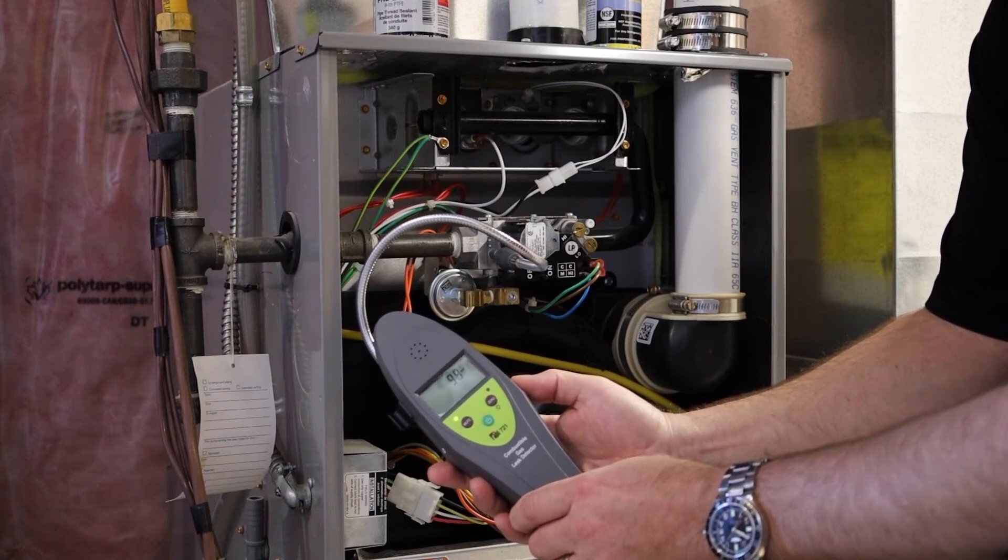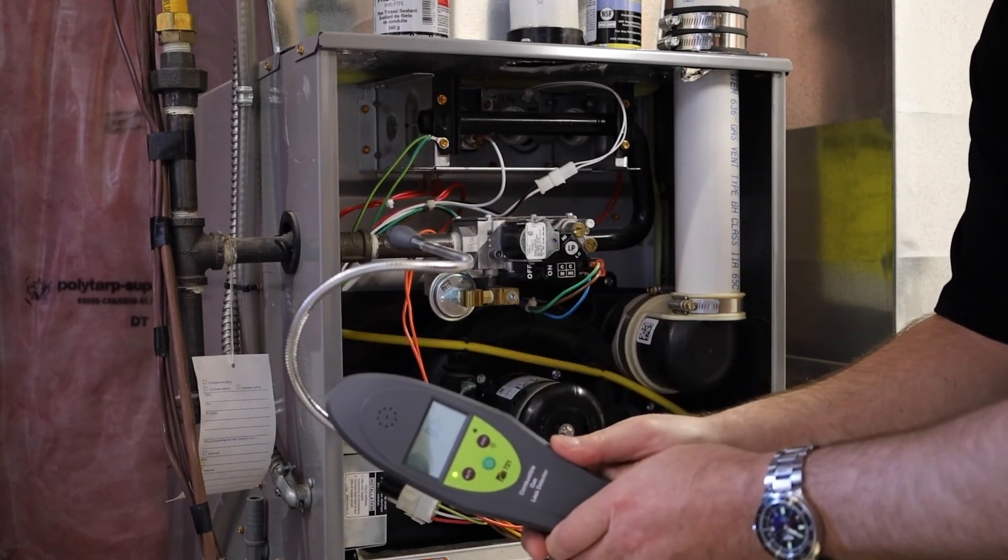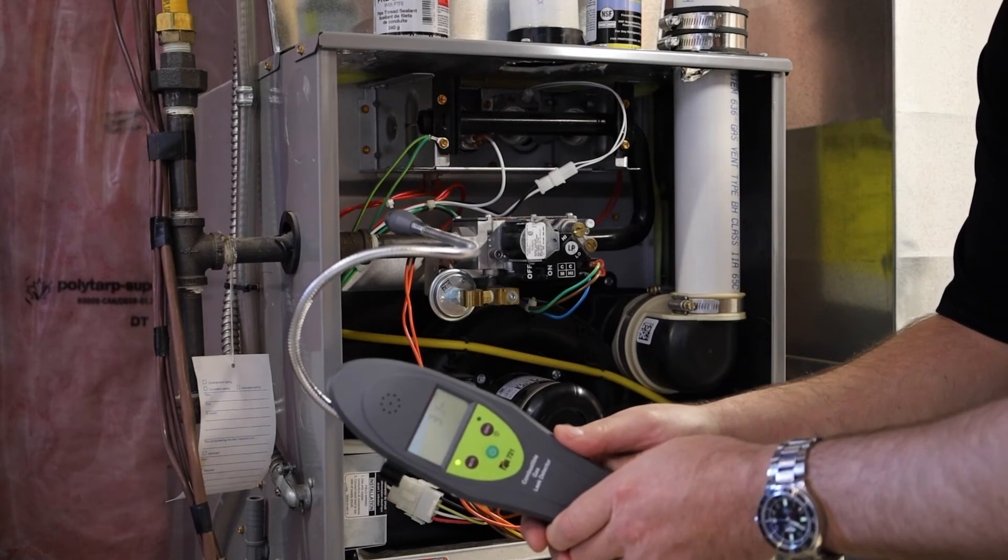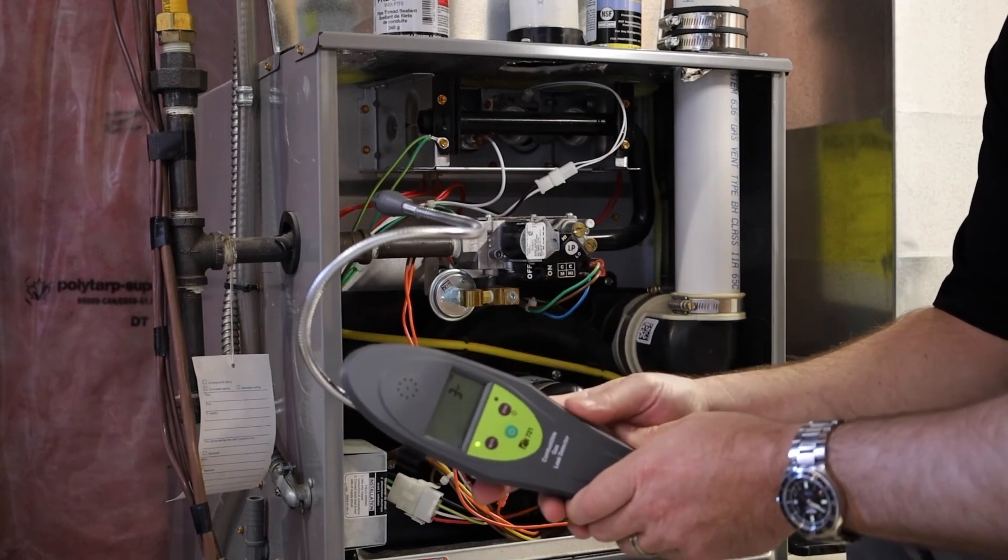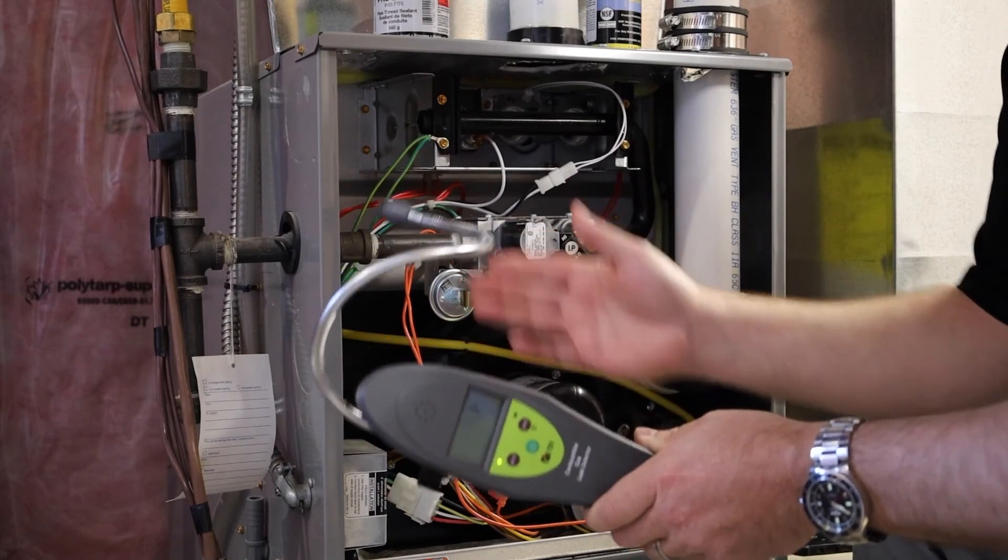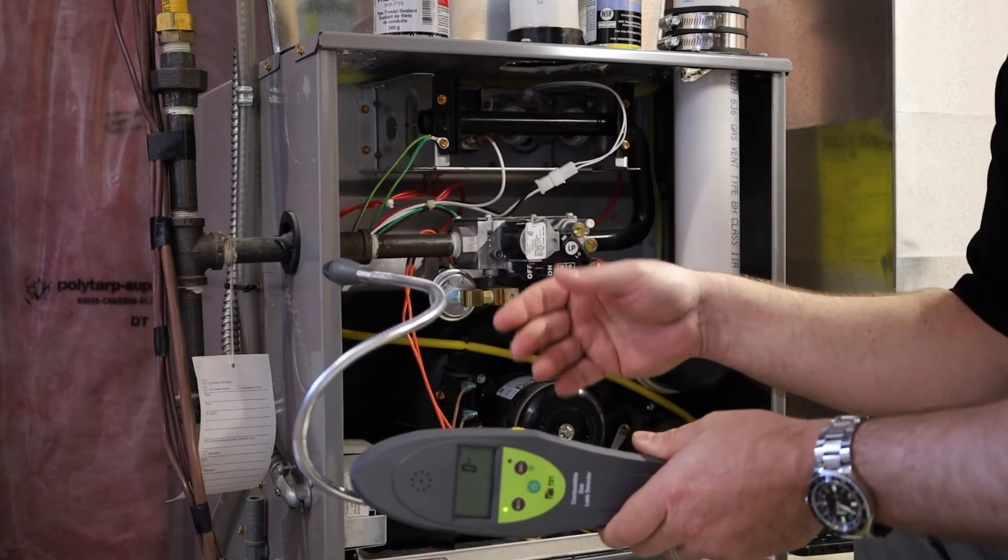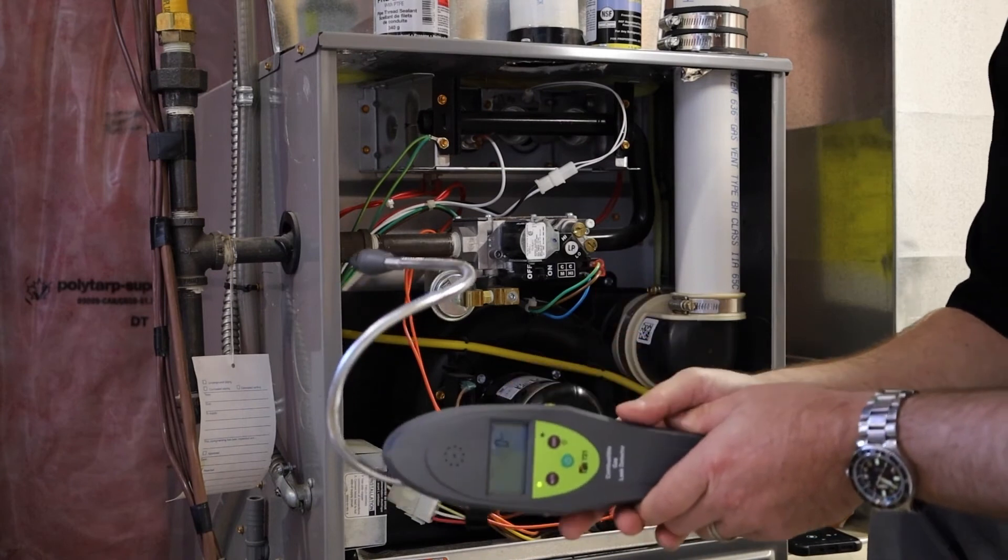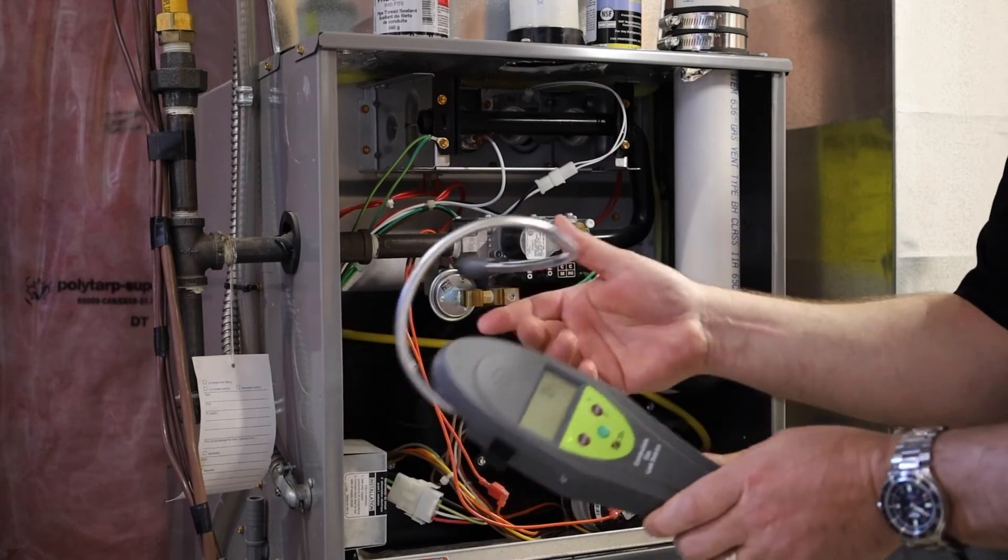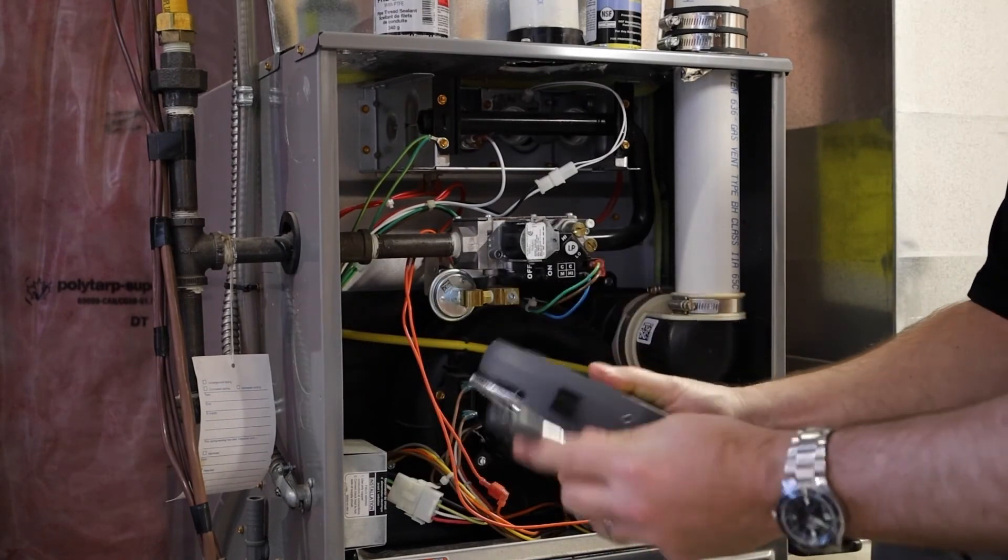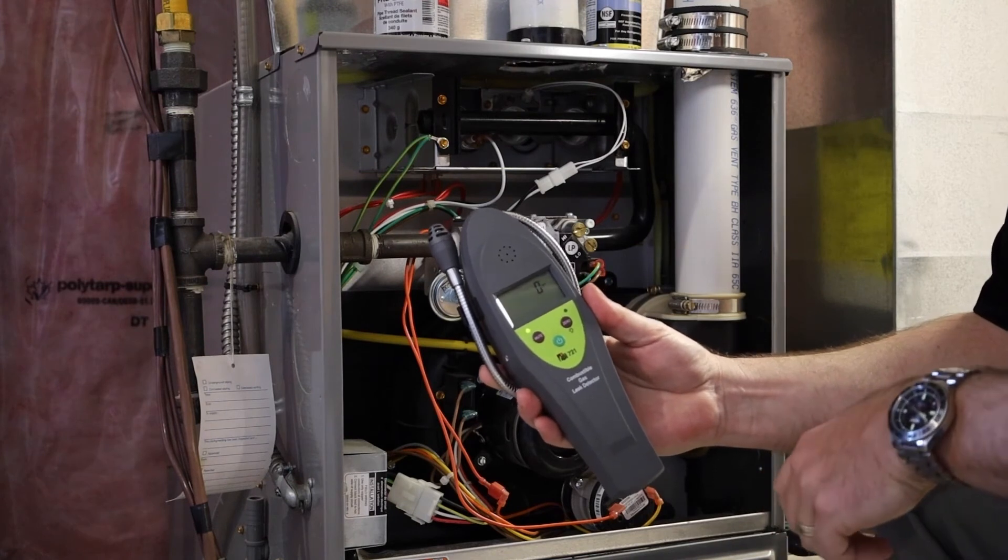Right now that gas, I'll just open up a little bit, is a very small leak. And leaks like this, very small leaks are really hard to find when it comes to using soap. I use soap in conjunction with my combustible leak detector, because not always can I use soap where I can see it. It could be on the other side of the pipe. It could be in the ceiling of a basement, or where it's coming out of the wall for a gas stove. This is where the electronic leak detector is more dominant. So that's the 721 combustible gas leak detector.